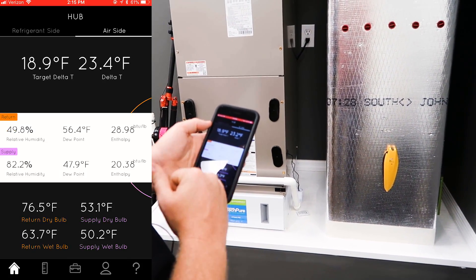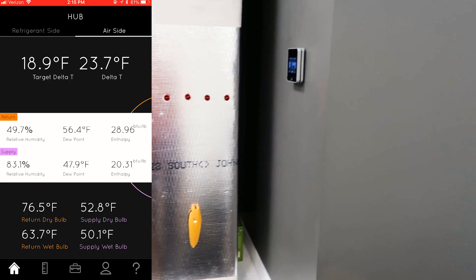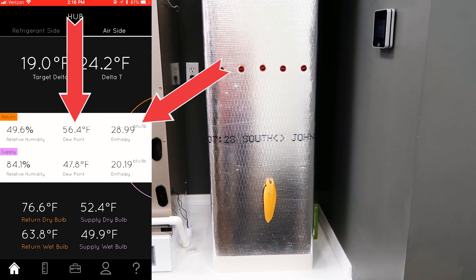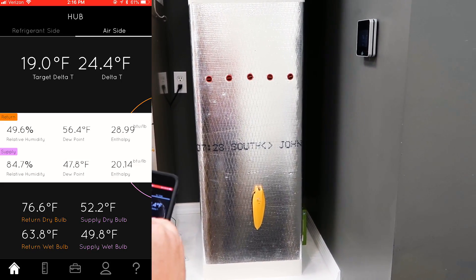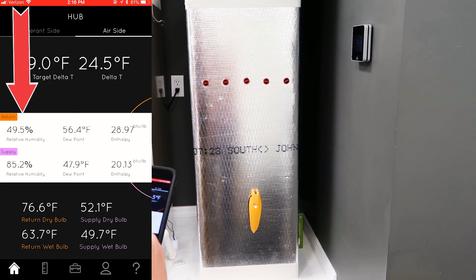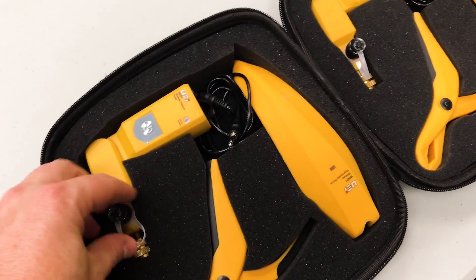I like how it lines up the return and the supply so you can see them right next to each other. When you look at changes in enthalpy and changes in dew point, you can tell it's removing moisture because the dew point is changing. You can also see it's removing heat because enthalpy is changing by 8 BTUs per pound of air. Relative humidity in the return is lower than in the supply, which is what you'd expect — that's normal.